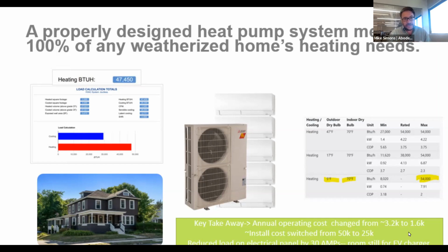The install cost of putting in one properly sized air source heat pump for my home, with each mini split roughly $4,000 to $5,000, changed the overall install cost to what I paid, about $22,000. If I hadn't done any of those weatherization improvements, it would have been closer to $40,000 or $50,000. So there's a direct correlation between install cost and operating cost when adopting air source heat pumps in a well buttoned-up home.